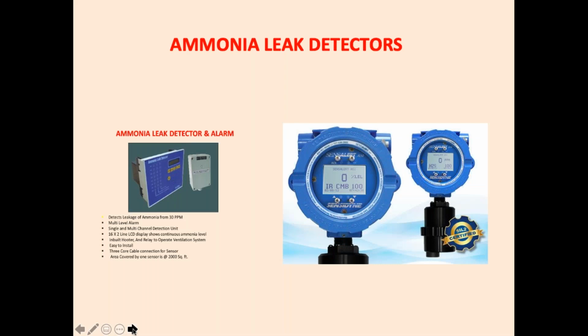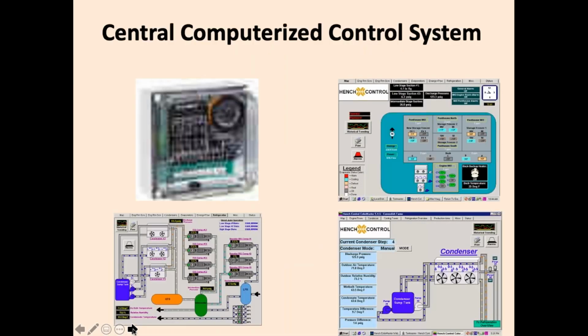These are the ammonia leak detectors. This is a centralized computer control system. You can see on the control panel the entire PNID has been printed: air coolers, pressure vessels, compressors, intermediate vessels, etc. And then you can read any temperature, any pressure, or record it from these panels. These are very advanced panels and they should be used wherever possible.